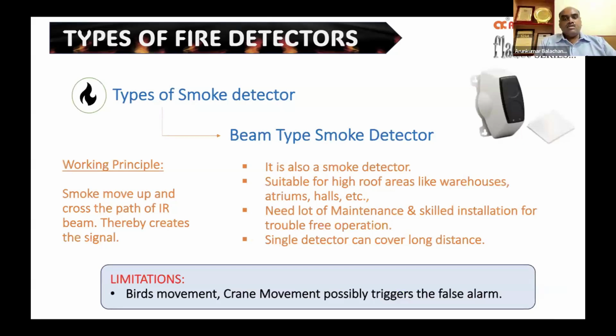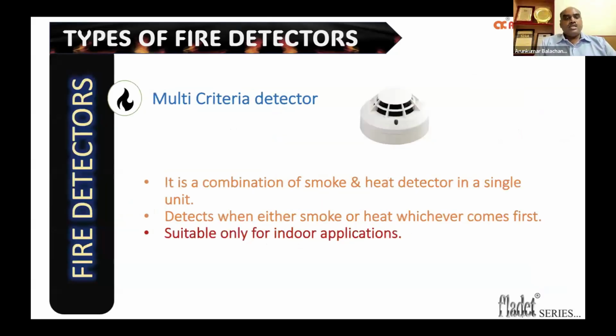We'll go in for the multi-criteria detector. So this is a combination of smoke and heat detector in a single unit, where either detection of smoke or heat can be prioritized, or a combination of smoke and heat can also be set. But being a smoke detector, it is also suitable only for indoor applications. And all the limitations of a smoke detector are applicable to this detector also.